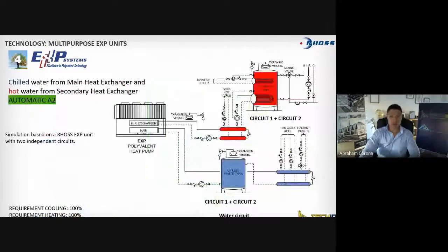How will that look in the water circuit? This is basically, if you see on the bottom, the same simulation. Now we have 100% demand of cooling and 100% demand of heating. Basically, you can see that the fans and the air-cooled condenser are now off, and we're cooling circuit 1 and circuit 2, and we're taking all that heat to heat the water in the heating tank. I'll also add a parenthesis here. You can see this is a standard, let's say, diagram connection for the water system.